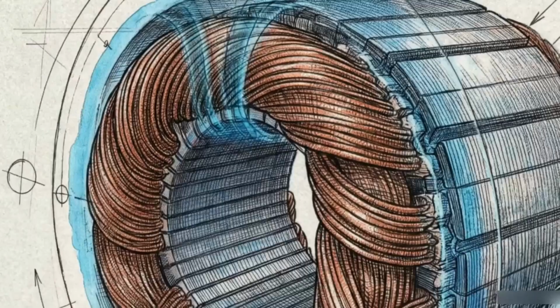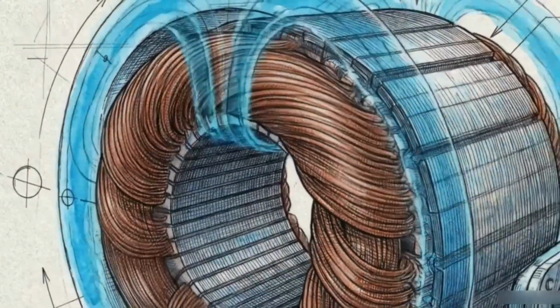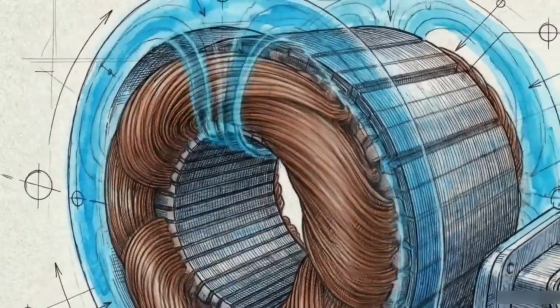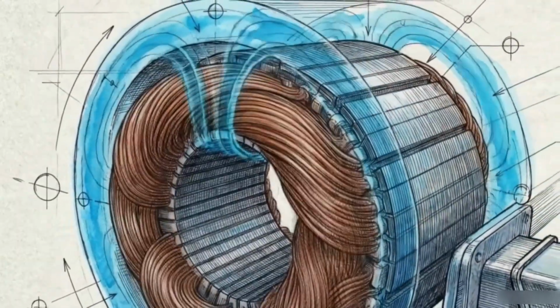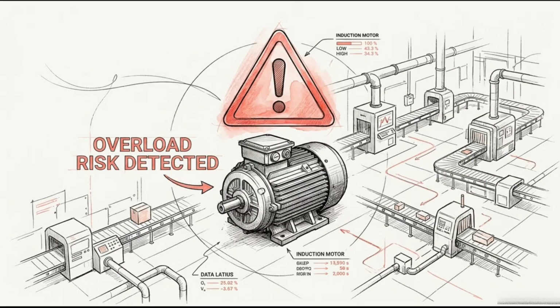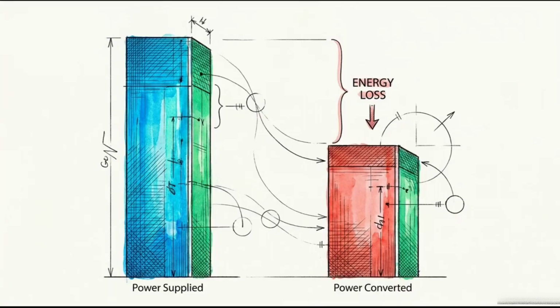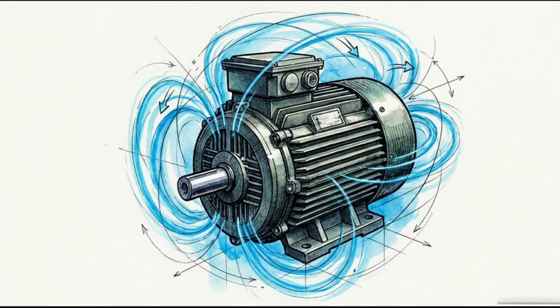Transformers and servo stabilizers are rated in apparent power, kVA, while the mechanical work done by a motor is measured in real power, or kilowatts. Because industrial motors use electromagnetism to turn, they draw more total energy from the transformer than they convert into physical motion. Tracking the gap between apparent and real power is how an engineer prevents a facility-wide overload before a single machine is turned on. The gap between the power supplied and the power converted into work represents a significant inefficiency. Inductive motors must maintain a magnetic field to operate, and that field is sustained by reactive power.